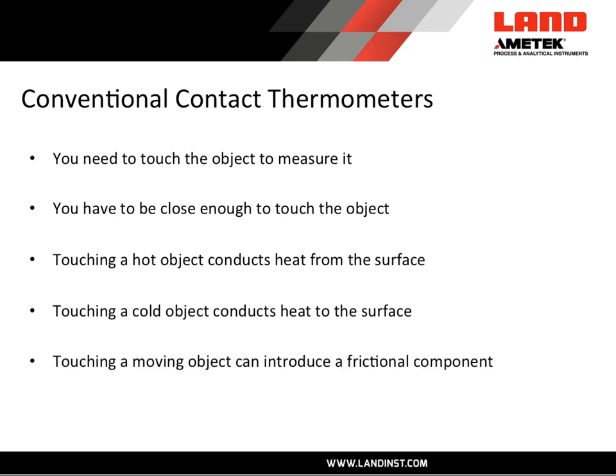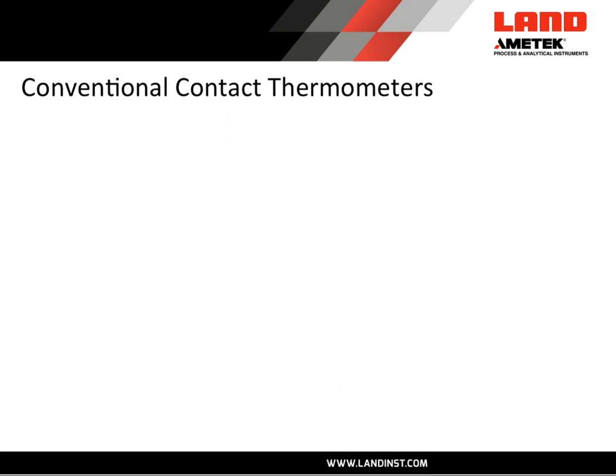In a similar way, if you're trying to measure the temperature of a very cold object, that thermocouple can conduct heat to the surface and warm that area, so the reading is falsely high. If you're trying to measure the temperature of a moving object with a thermocouple, that can be very difficult because there'll be a frictional effect from the surface scraping along that product. Also, with contact thermometers you can damage the object by touching it — for instance damaging delicate plastic — or you could contaminate it, which would not be good for food or pharmaceutical products.